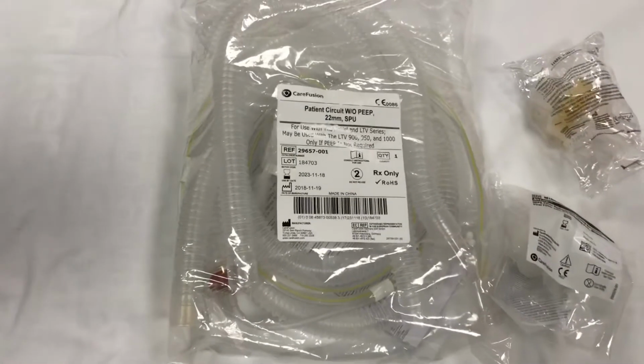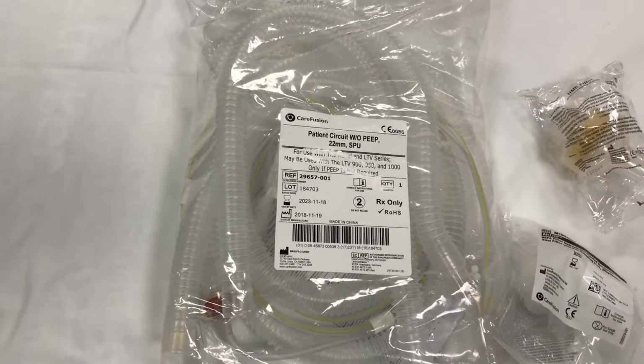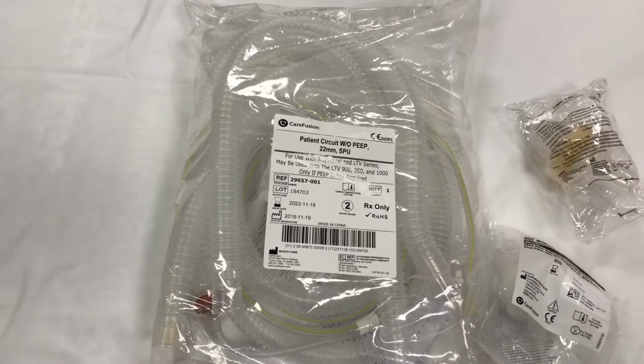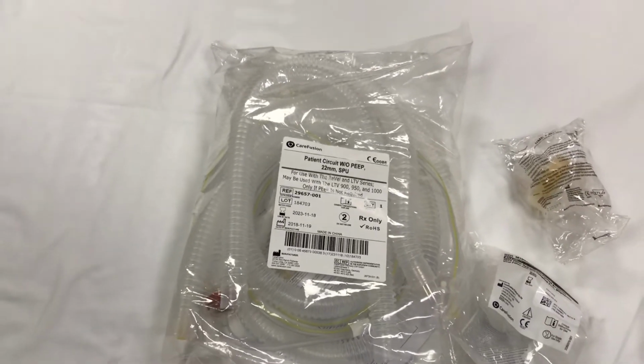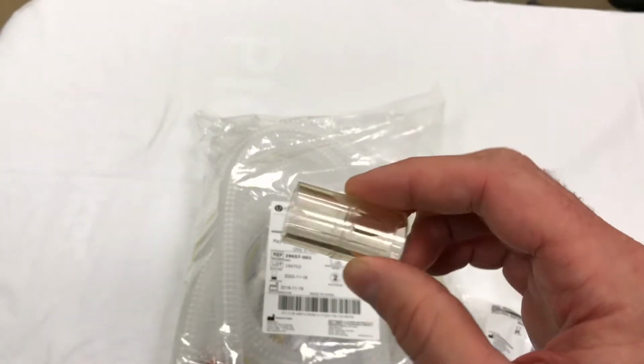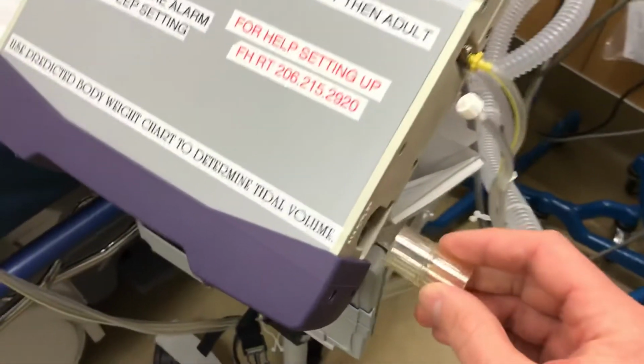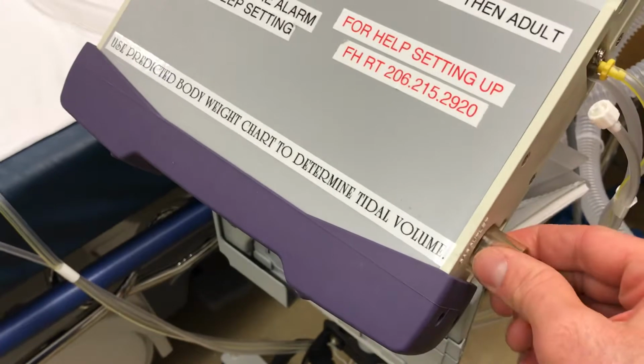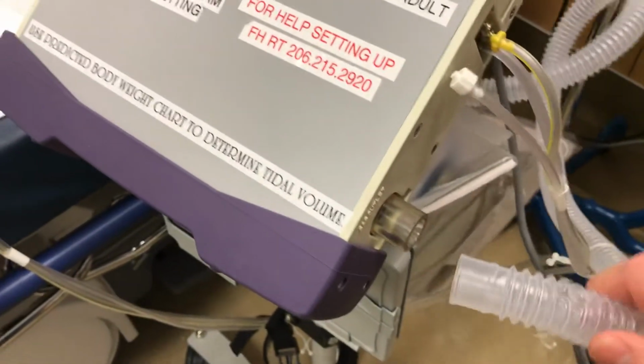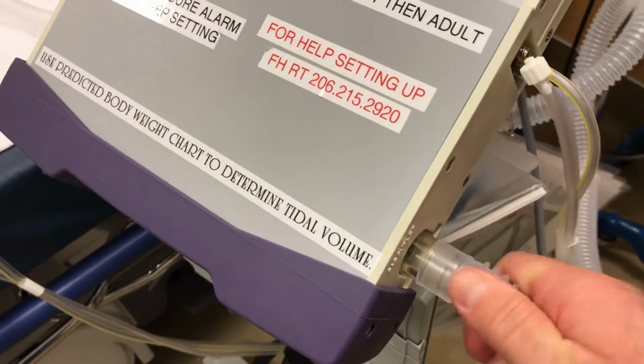Just in case you don't have any help, the first thing you want to do is unpack the patient circuit. Uncoil all the tubes. Make sure you fish out this 22 millimeter hard plastic port. It goes down on the right side of the ventilator. Otherwise you won't be able to connect the corrugated plastic tubing.